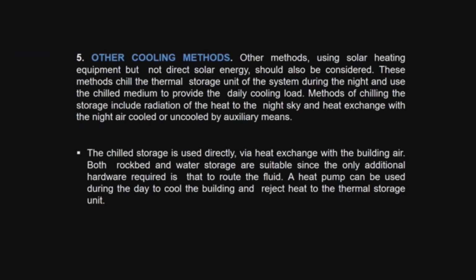Other cooling methods. Other methods using solar heating equipment but not direct solar energy should also be considered. This method chills the thermal storage unit of the system during the night and uses the chilled medium to provide the daily cooling load. Methods of chilling the storage include radiation of the heat to the night sky and heat exchange with the night air, cooled or uncooled by auxiliary means. The chilled storage is usually used directly via heat exchange with the building air.